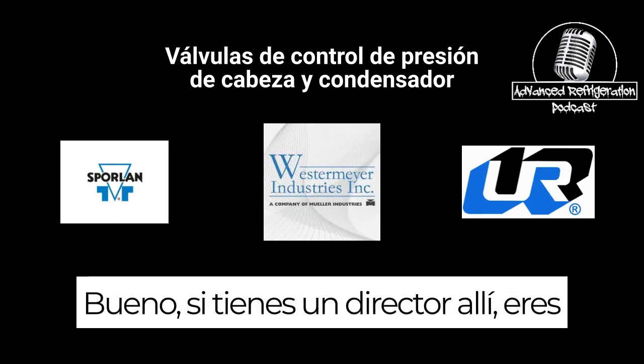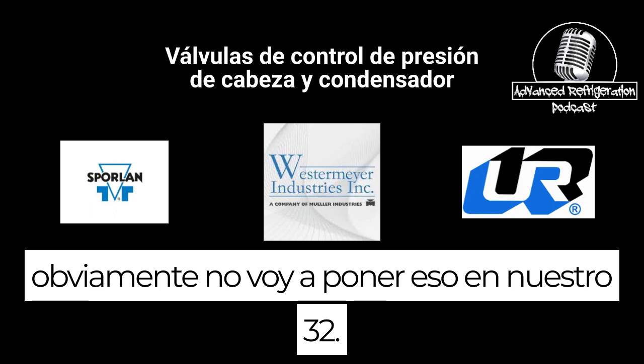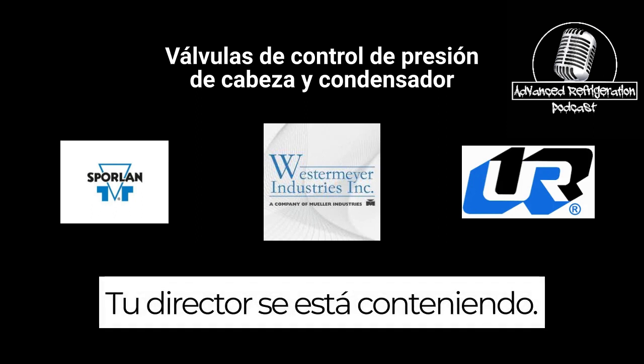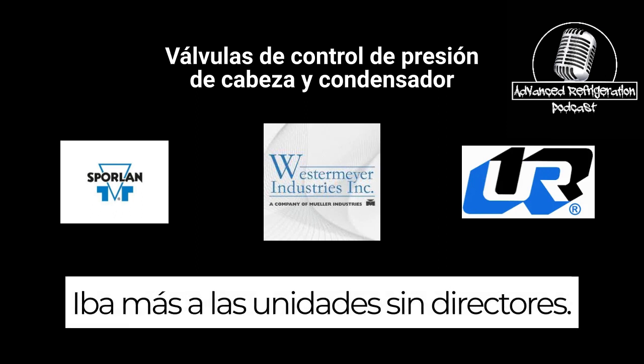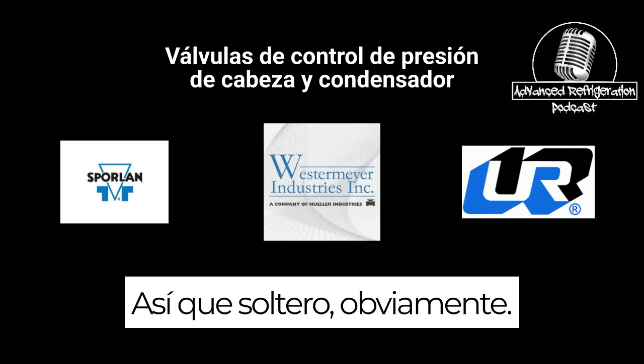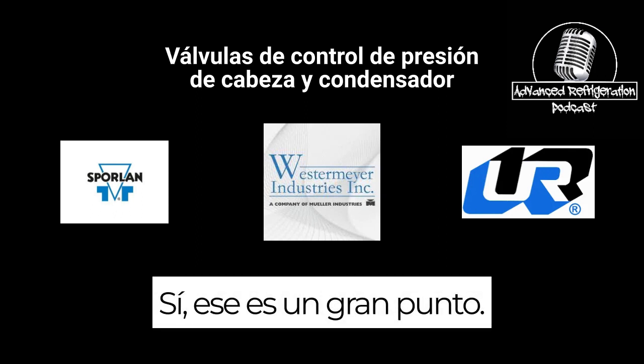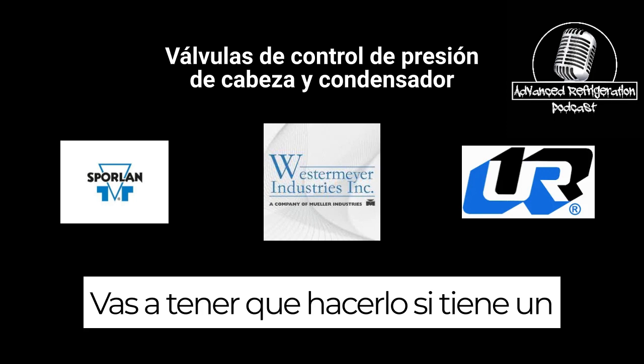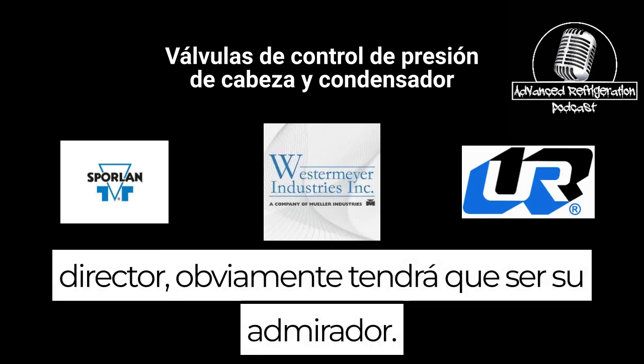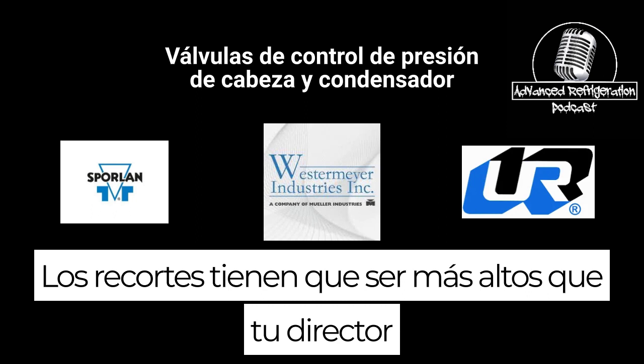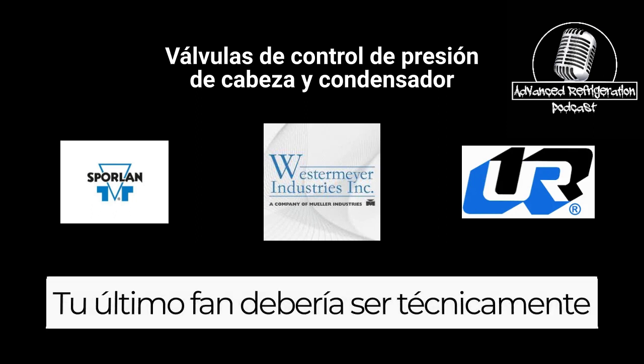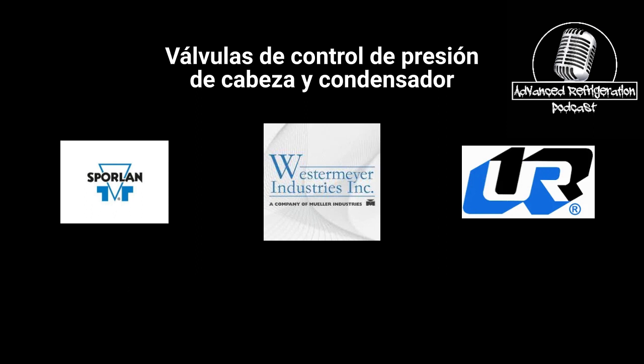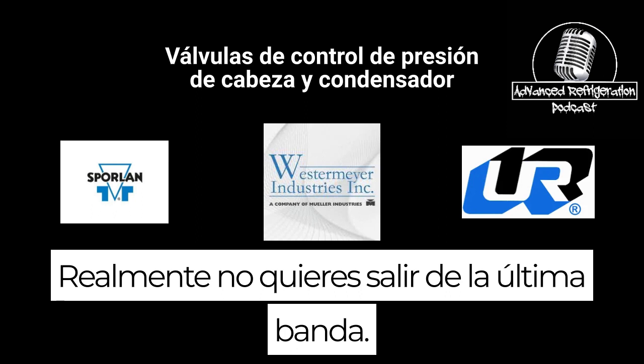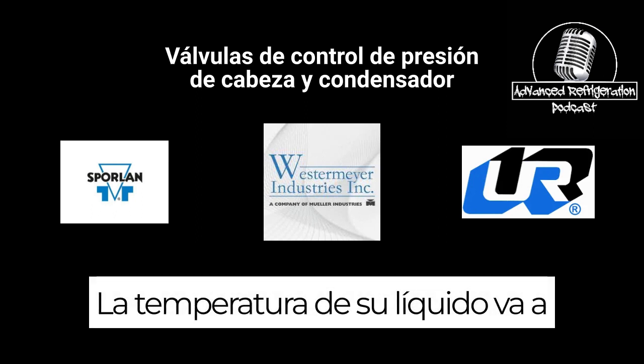Well, if you have a headmaster on there, you're not going to obviously put that for 132 if your headmaster is holding back. Correct. I was going more so over units without headmasters. Okay, so just single units. Yeah, that's a great point. If it has a headmaster, your fan cutout has to be higher than your headmaster, or they're going to fight each other. And your last fan should technically be on for that headmaster to work. You don't really want to cycle off the last fan. Your liquid temperature is going to be all over the place.